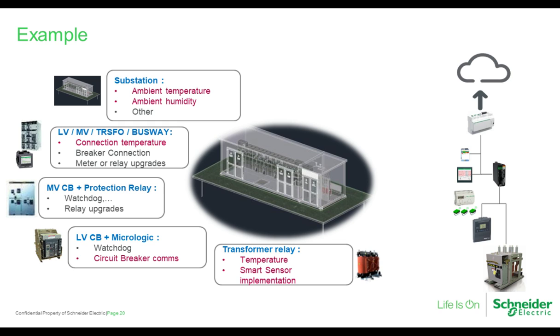Or we can add smart sensors to the transformer. Many dry type and liquid filled transformers have temperature sensors that either monitor the winding temperature for a dry type, we can add that into the system, or for a liquid filled, either the oil temperature and or the winding temperature. So those are different ways to do that. And then with all of these devices we're adding to the system, we can now bring them all up to the cloud for additional monitoring by either the plant engineer, the plant maintenance, or an outside concern that will help make decisions for the future on how to maintain that equipment and to keep it up and running and reliable and safe.